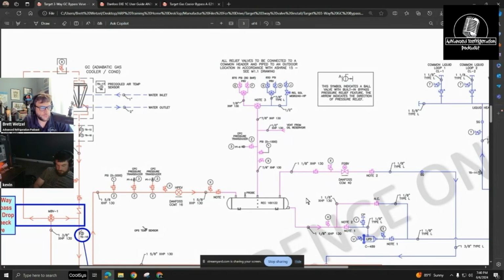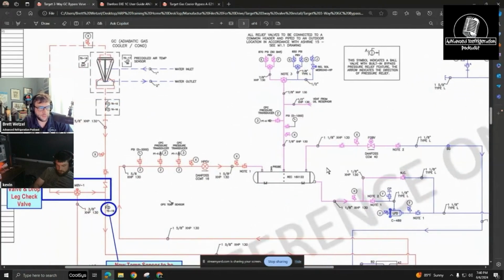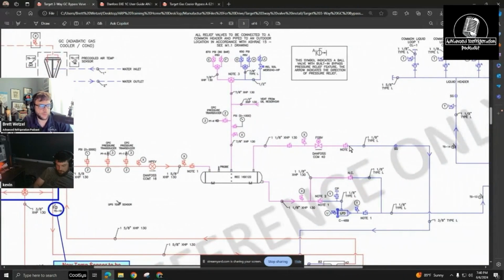If you look at these prints, be advised that here it tells you what the piping designation is. So you have type L here and type XHP right here, which technically means if you're going to utilize this, that pressure can't be on the other side of this valve or this valve, right? Because you have XHP back here, correct, XHP here, and then you're with L here.